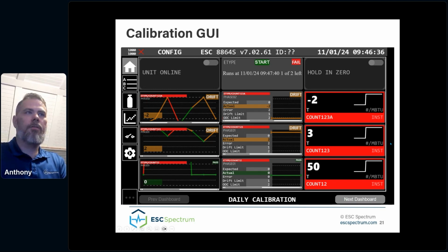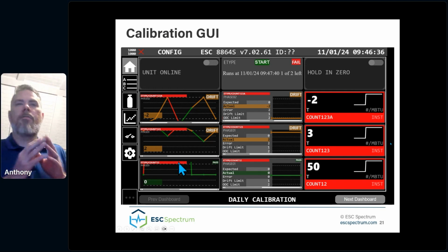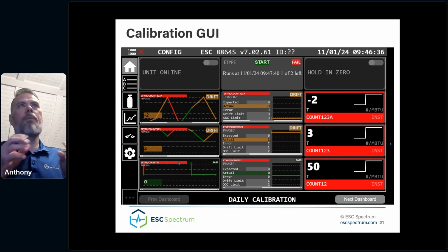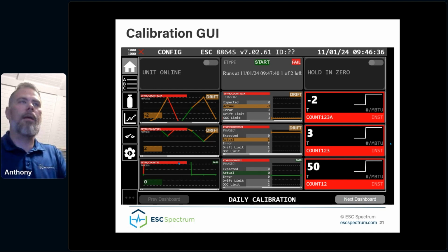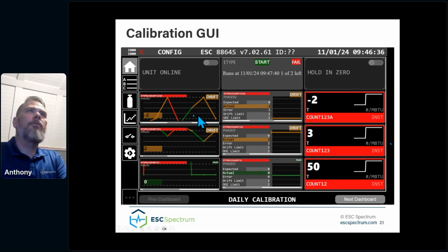Okay, for this trend view, we'll see a graph showing calibration results for the configured channel for the last configured number of data points. So again, this is per channel, but it allows you to navigate through all of the phases for that channel within that calibration. And the default for this is 14 data points. So the trend will give you a view of your last 2 weeks of calibration runs. Each one of these data points represents that channel's value for that phase, what the result of that run was.